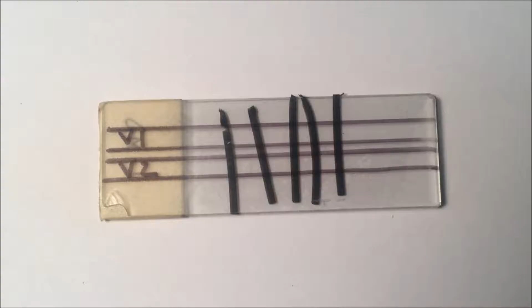Each one of these specimens will be viewed in 2 different views, an A and a B, and you'll use an overlay slide for that on the microscope. So now we'll go into viewing this under 100x magnification. Again, 5 specimens, 2 fields of view, so there are 10 readings in all. You will then categorize these readings using the ASTM chart.